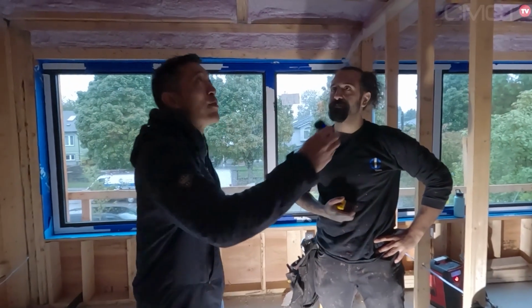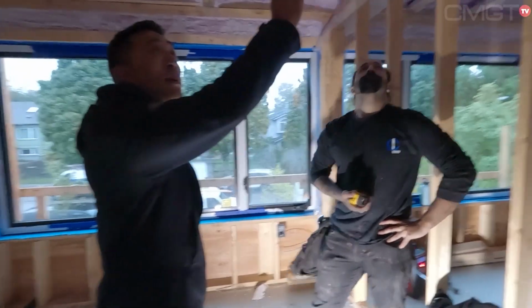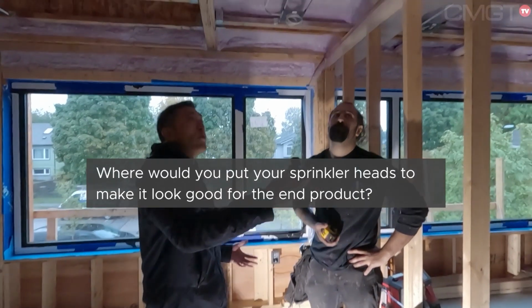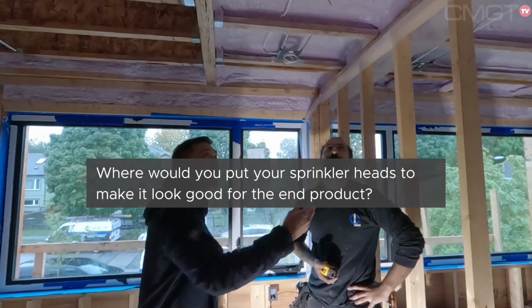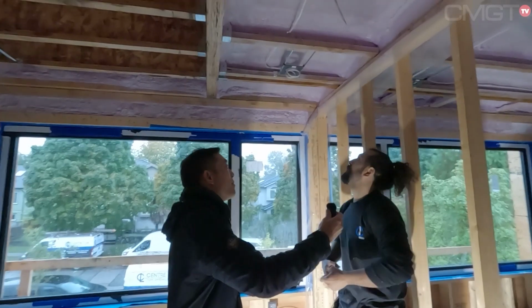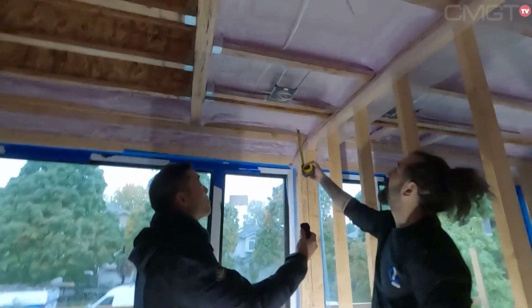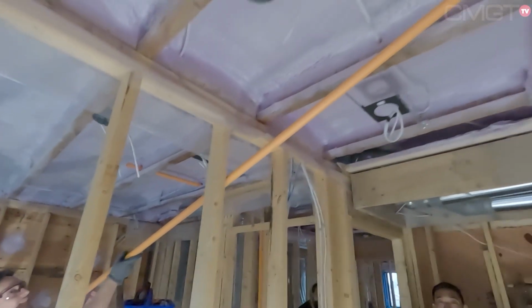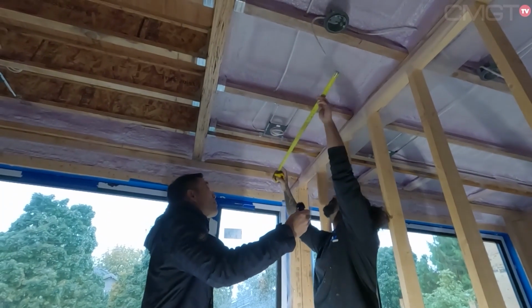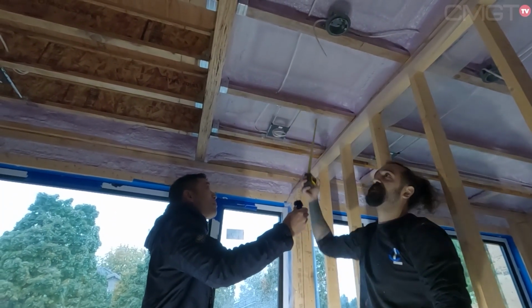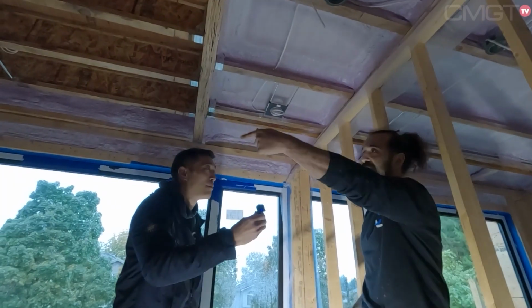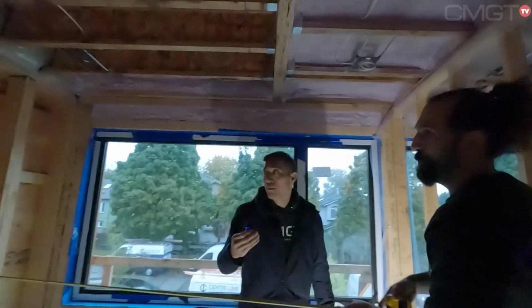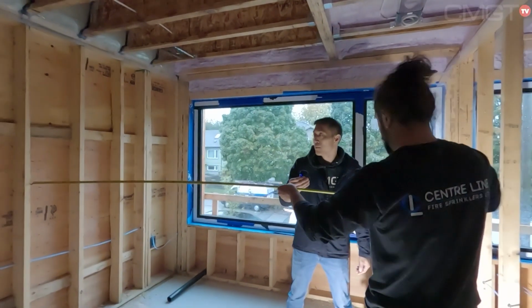Okay, so for example, this room here, we have the lights, we have a smoke detector, a square room. Where would you put your sprinkler head to make it look good for the end product? Well, obviously you'd always want to try and line up with a light or a pendant or a smoke detector, whatever it is, and put it in the center. Measure right here and see where the center is, put it right there, and if that covers all the way up to that wall, then it should be good.